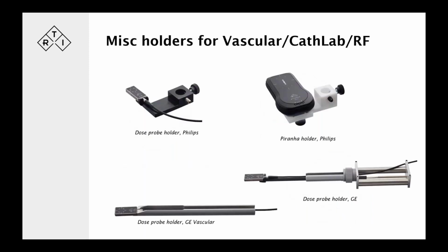Then there are some other miscellaneous holders that we found are pretty popular. For Philips, there is a holder that fits onto their vascular and their cath labs. There's a rod on that EDL kit, and this goes onto there, and we have the dose probe at the right reference height. Or we can do the same with the Piranha, have the Piranha detector at the right reference height as well. So that's for Philips. Those are available for GE, and it's typical to find a GE vascular holder, which goes onto the vascular, the Innovas, that fits into those test jigs that GE have for that. And the same thing goes for the dose probe holder for the RAD, and sometimes also for the older mammography testing kits. So these are the ones that are referred to in the technical manuals of these manufacturers.